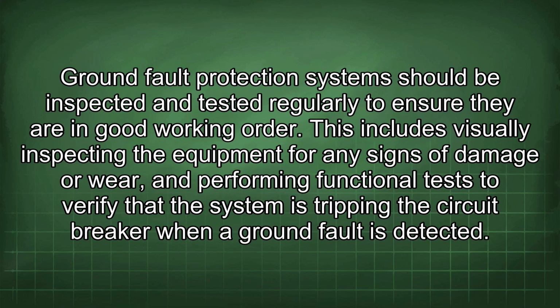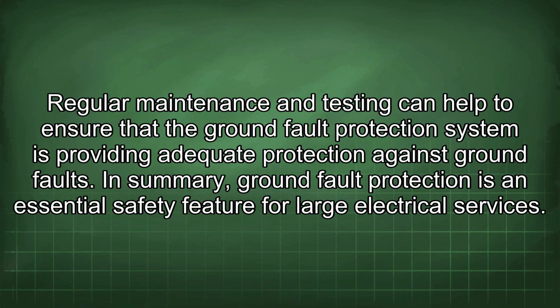Ground fault protection systems should be inspected and tested regularly to ensure they are in good working order. This includes visually inspecting the equipment for any signs of damage or wear, and performing functional tests to verify that the system is tripping the circuit breaker when a ground fault is detected. Regular maintenance and testing can help to ensure that the ground fault protection system is providing adequate protection against ground faults. In summary, ground fault protection is an essential safety feature for large electrical services.